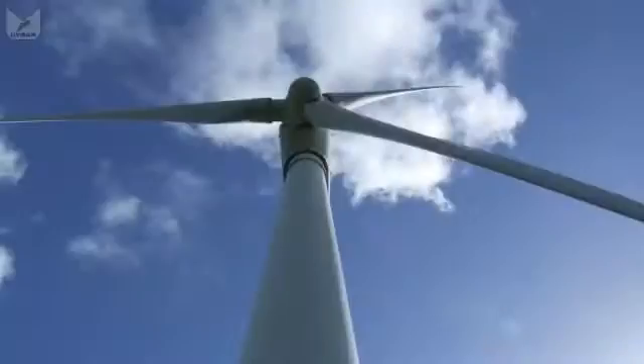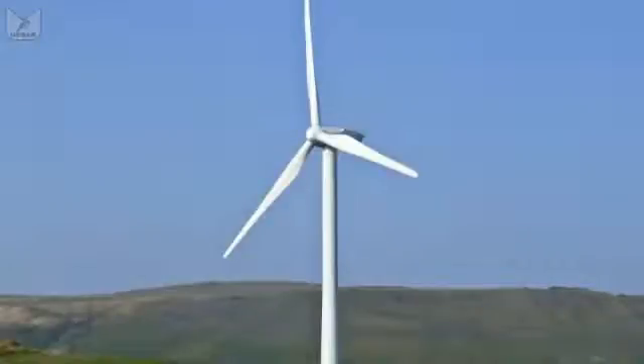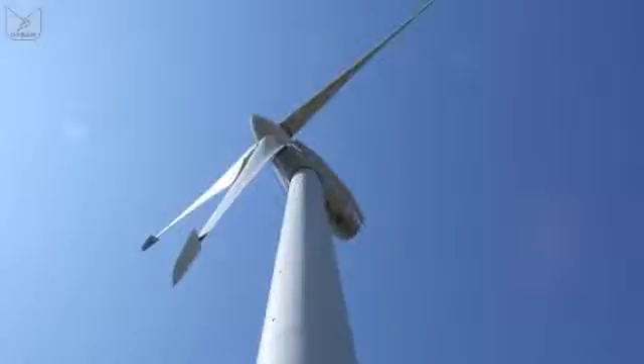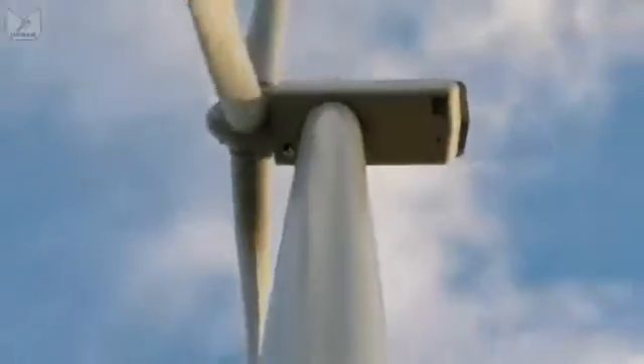Now exact designs do vary, but almost all the turbines in use today are horizontal axis machines which have a three bladed rotor spinning in a vertical plane attached to the front of a box which we call the nacelle, after the fairing around an aircraft engine. In this nacelle we have the generator, often a gearbox, and occasionally a high voltage transformer. The whole thing sits on top of a tower which is mostly there to keep the blades from digging a hole.